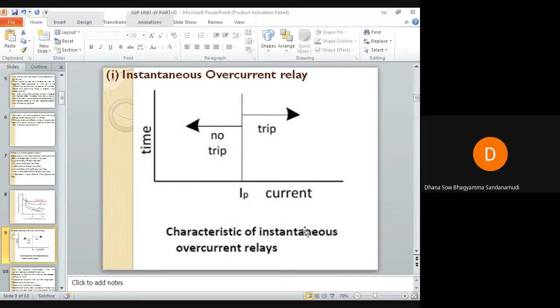This relay operates instantaneously when current exceeds its pickup value. Its operation criteria is only the current magnitude — operating time is constant and there is no intentional time delay. Coordination of these relays is based on the fact that fault current varies with the position of the fault because of the difference in impedance between the fault and the source.